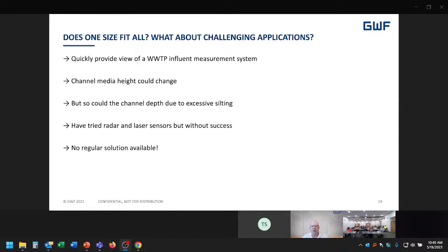I'll give a quick overview of a wastewater treatment plant influent measurement system. The customer had tried a couple of other sensors without success, because the channel media height—the flow height—could change, as happens in a lot of systems, but the real challenge was that the channel depth could change due to excessive silting.